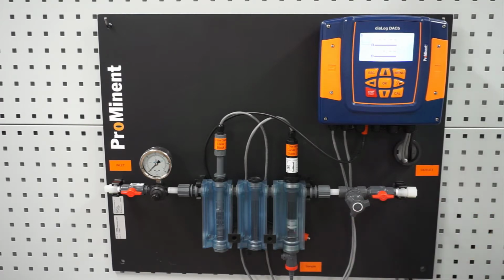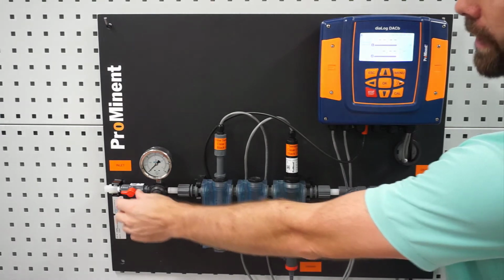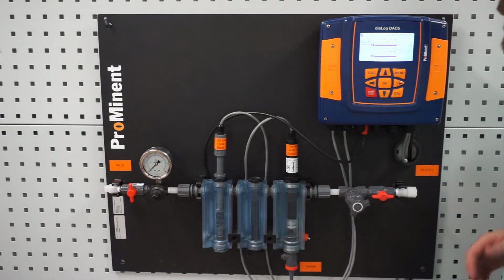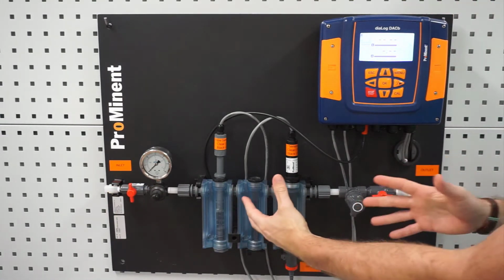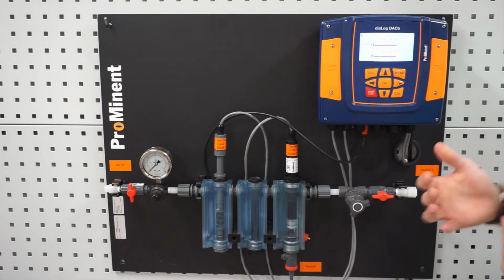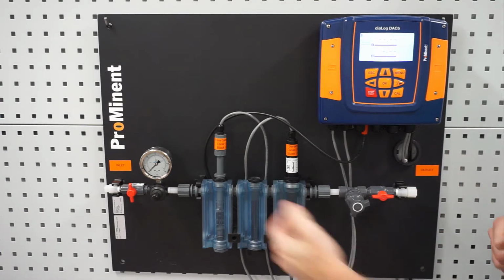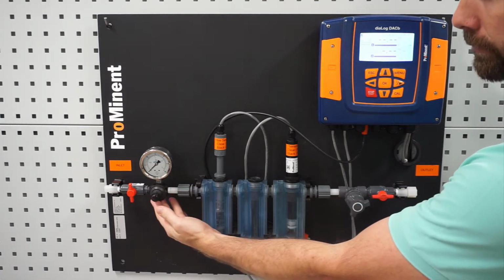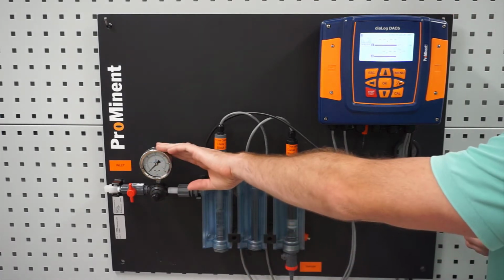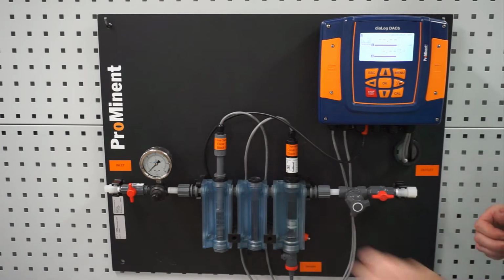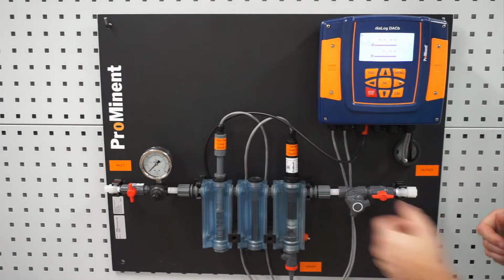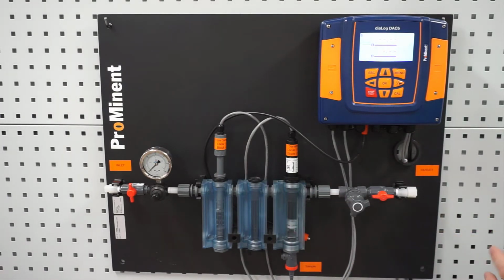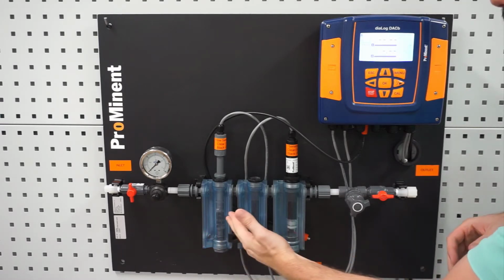Looking first at our flow cell, you can see all the way to the left we have an isolation valve. That would allow us to valve out the water so that we can access our sensors without water flowing all over the place. Next is a pressure regulator. And on that regulator is a gauge. Our amperometric sensors, in this case our chlorine sensor, are very sensitive to pressure. Too much pressure is going to affect the electrolyte in our sensor, so we'll talk about how that gets set up. After that we have a flow sensor.